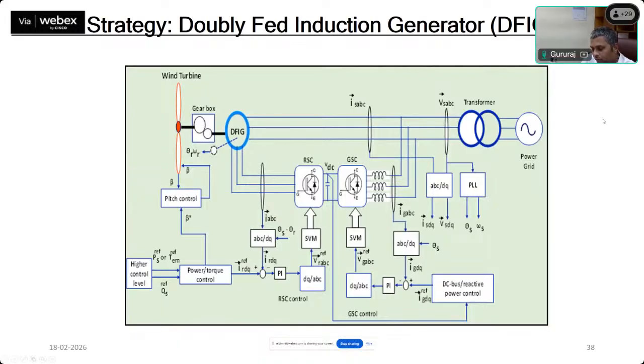And if there is no fault, then this fault current limiter is physically there but electrically gets disconnected, so it may look like a small resistance being connected in series, which is not so significant. So they indirectly do not consume much electricity from the grid during normal operation, but are of great help during grid fault conditions. What they actually do is limit the value of fault current being produced from the double fed induction generator, or they indirectly support the voltage collapse at the point of common coupling. Thereby, the impact on the grid and on the double fed induction generator can be reduced.